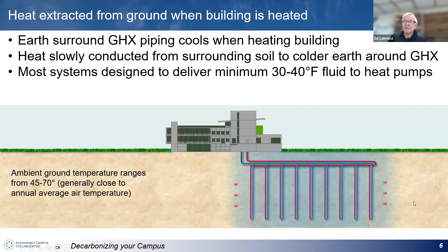There are a lot of different ways of moving heat to and from the ground. Vertical boreholes are quite common, depending on how much land area you've got available. They're drilling them up to about 800 or 900 feet deep, or around 300 meters in some areas. Depending on the geology, in other areas we don't drill much more than about 100 or 120 meters, but it really depends on the geology and what drilling contractors are available in that area.